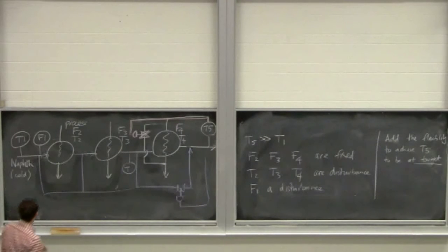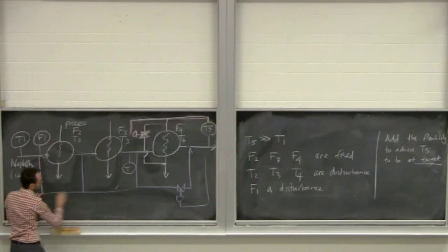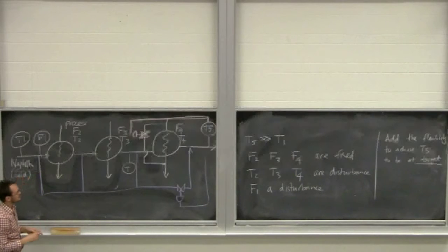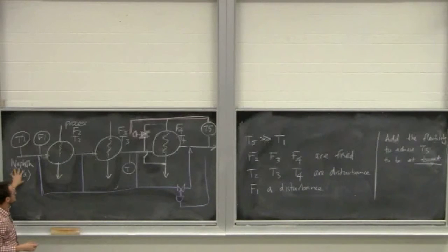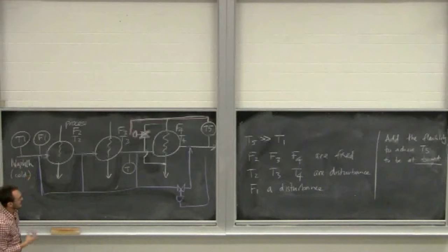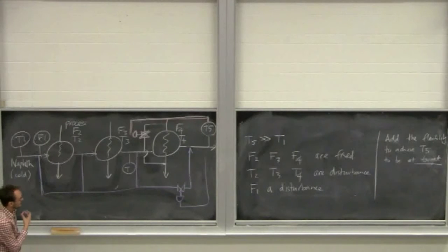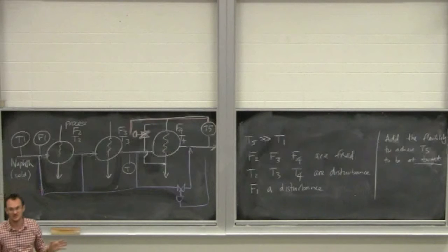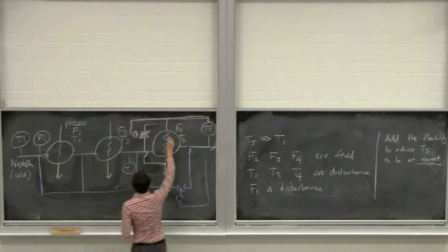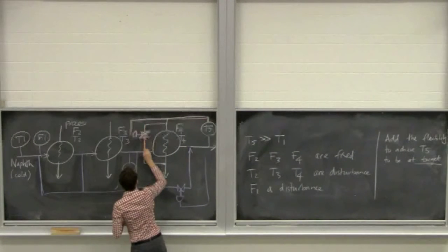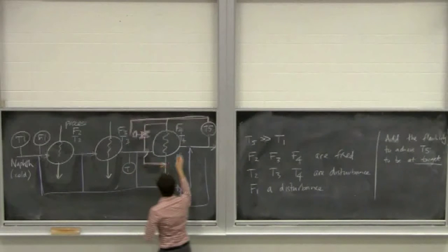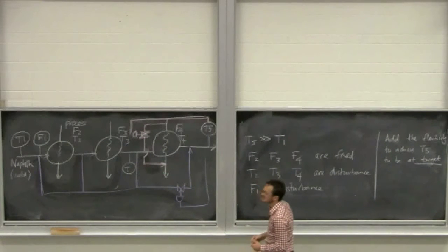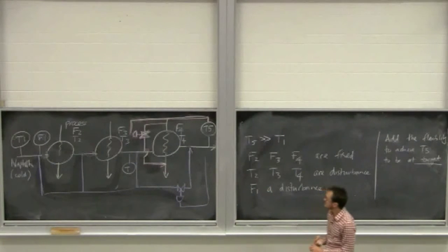With this configuration from here coming down first over here and then all the way across, I could go to basically bypass all the heat exchangers and I could go, even this valve here is fully closed, I'm using all three heat exchangers. So, it's a tremendously flexible range. The drawing here in red, let me just complete the rest of the red part, essentially bypasses the heat coming from the process stream.